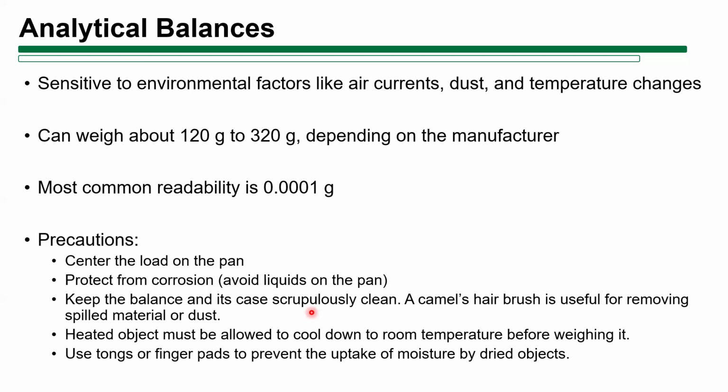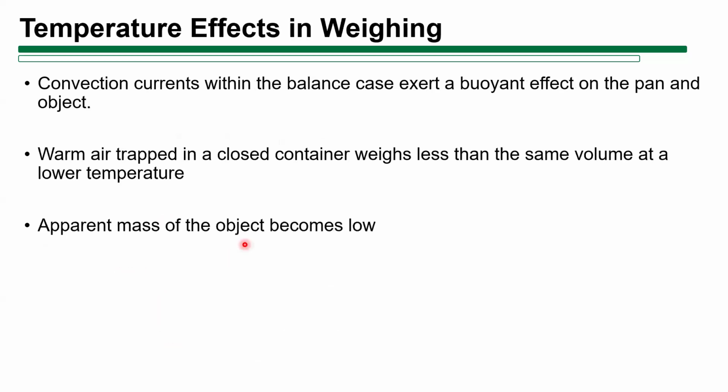Now, it's advisable to use tongs or finger pads to prevent the uptake of moisture by dried objects. All right, so these are the precautions to take note of when using an analytical balance. Now, I will just briefly talk about the temperature effects in weighing.